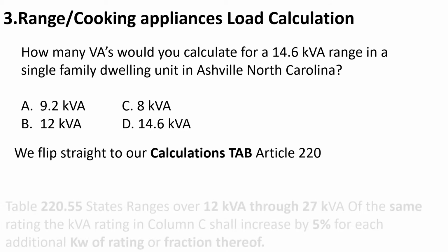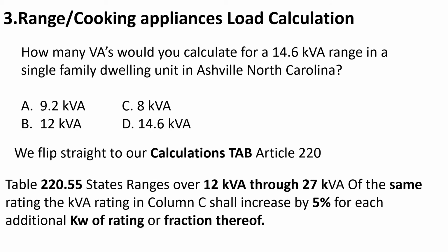How many VAs would you calculate for a 14.6 kVA range in a single-family dwelling unit in Asheville, North Carolina? So we've got some options. We flip straight to our Calculations tab in Article 220. Table 220.55 states that ranges over 12 kVA through 27 kVA of the same rating, the kVA rating in column C shall be increased by 5% for each additional kW of rating or fraction thereof.